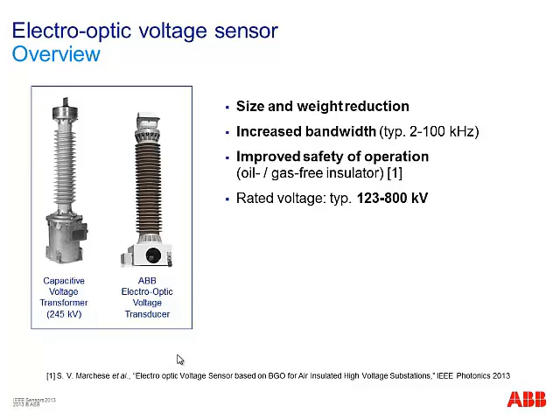The safety of operation can be improved because it's possible to make these sensors without oil or gas insulation, and this is a serious advantage, in particular in terms of environmental compliance. And as I've told, the rated voltages are the ones indicated here.